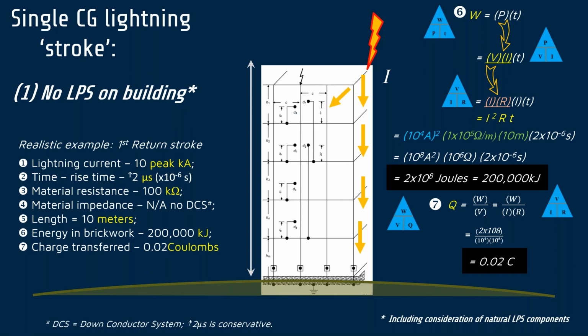Got that one right. So if this particular building with brick and mortar does not have any mechanical or metallic path by which that lightning current can go to ground, with a fairly fast rise time of 2 microseconds...